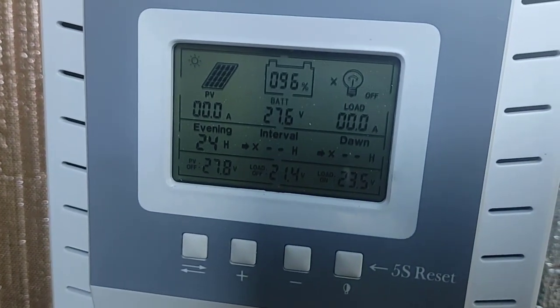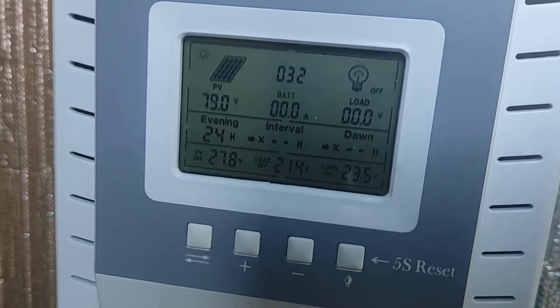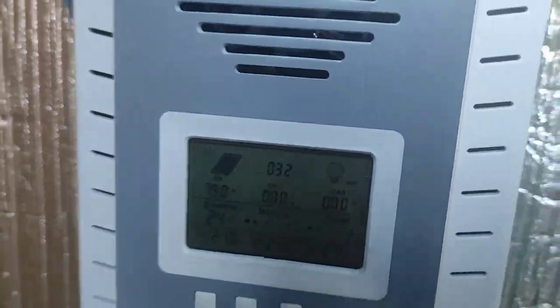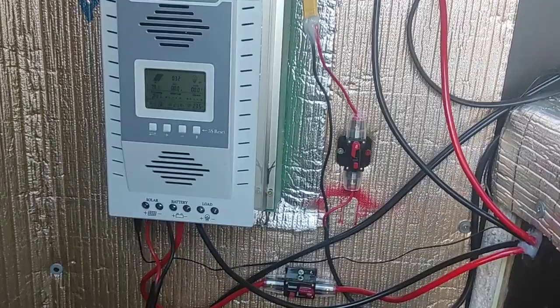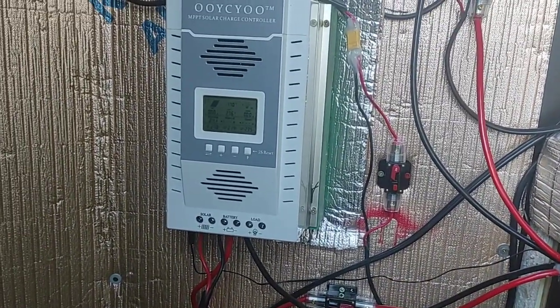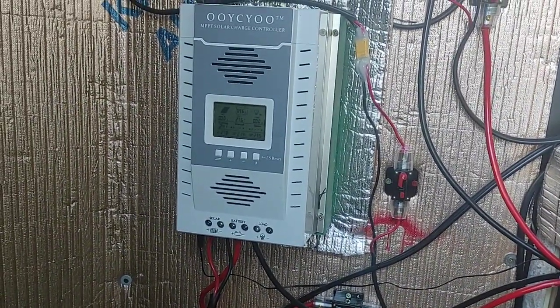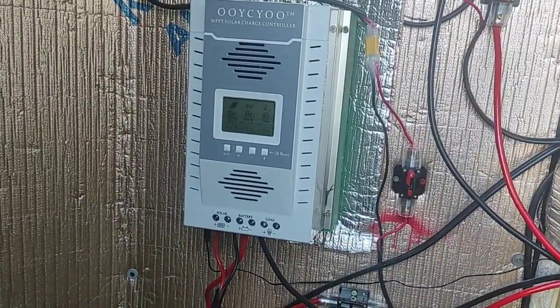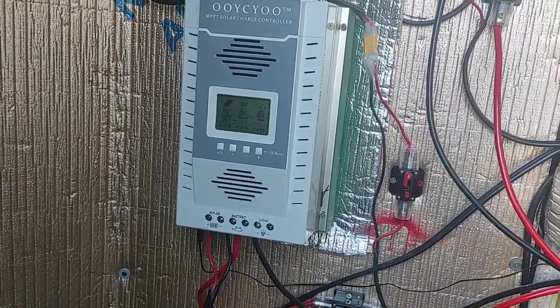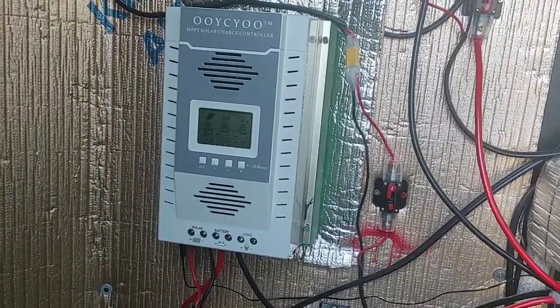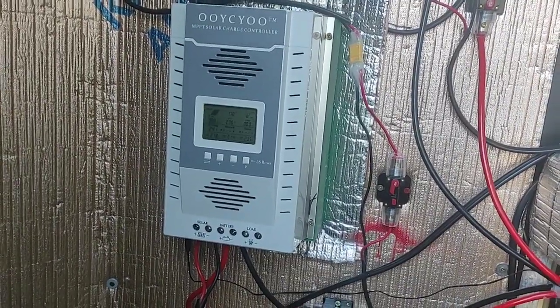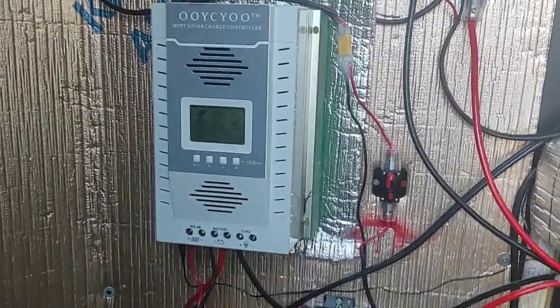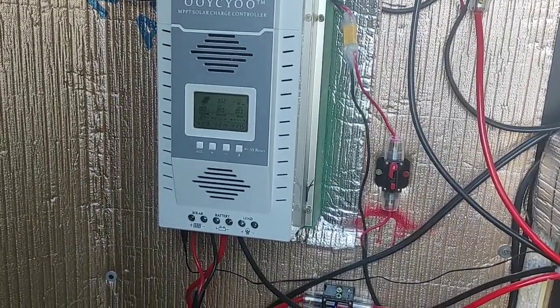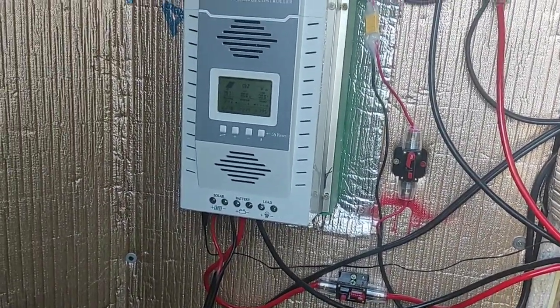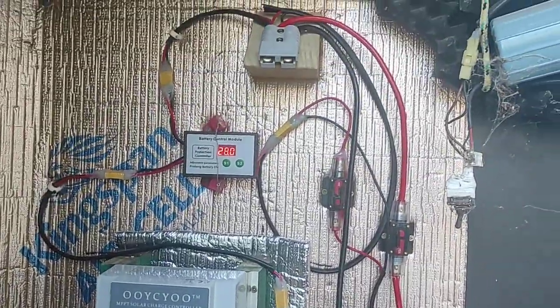At a 24 volt battery bank, this charge controller can handle 2600 watts of PV array maximum before you'll damage it, and then you get a bit of losses. Do that math, and it'll pump out 100 amps for the output charging. But it's been great how quickly this charges up, as you can see.